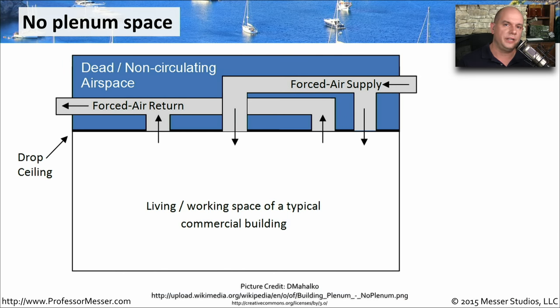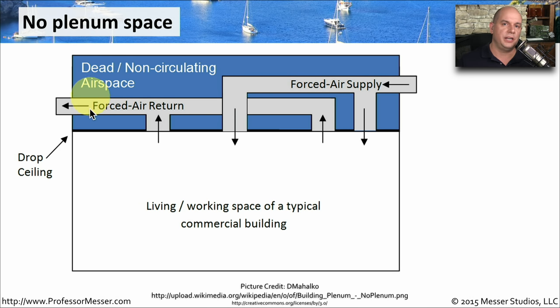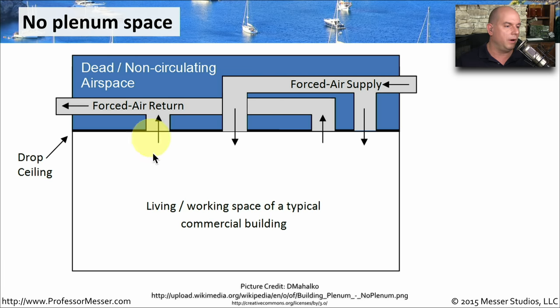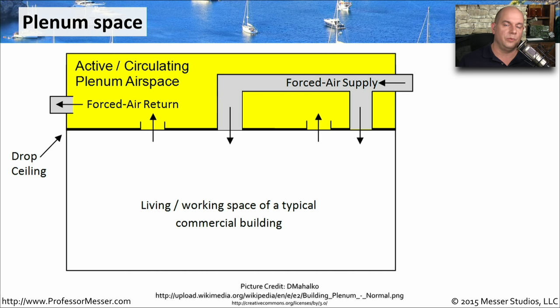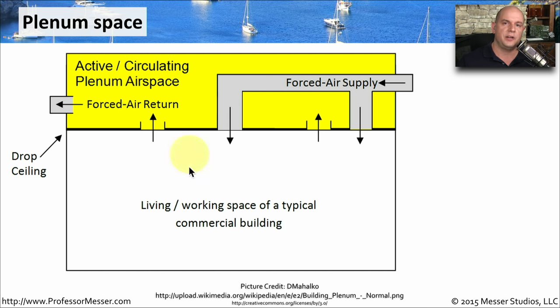In many commercial buildings, there's a space between the drop ceiling and the actual ceiling of the building that can contain pipes, air supplies, and network cabling. If your air system uses its own ductwork rather than that shared space above the ceiling, then you don't have a plenum concern. But some environments use that shared area above the drop ceiling as the return air path back to the HVAC system, and it's in that shared plenum where we are more concerned about the network cables that may be in this space.